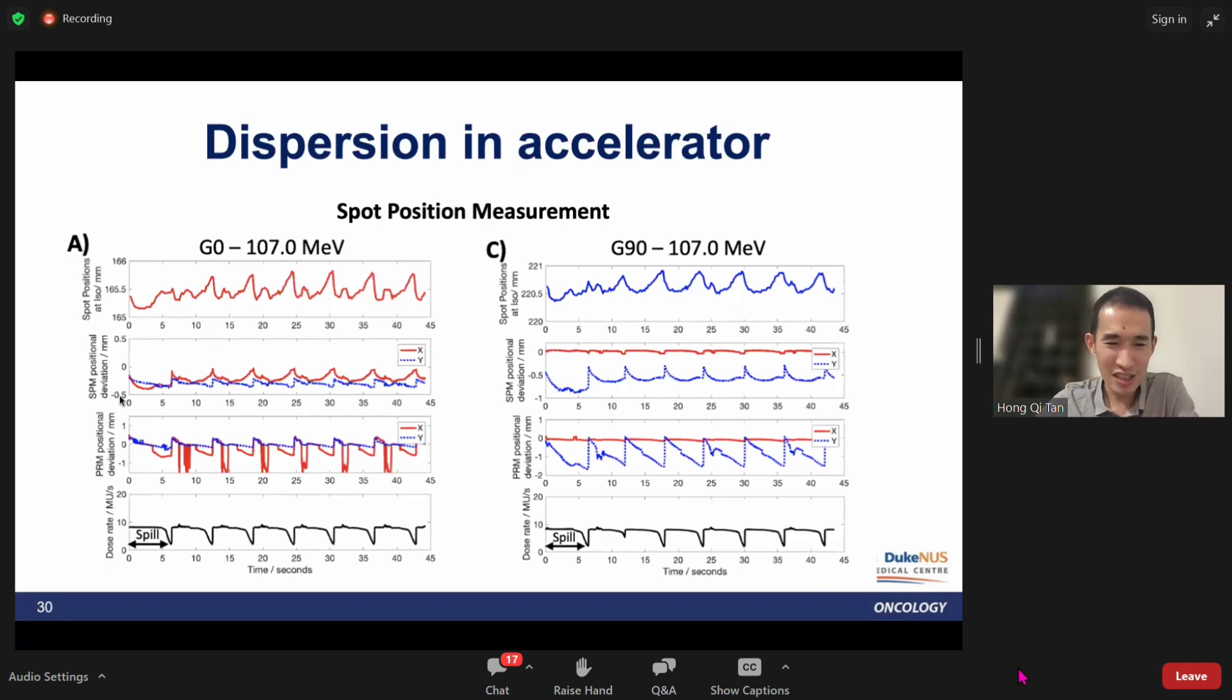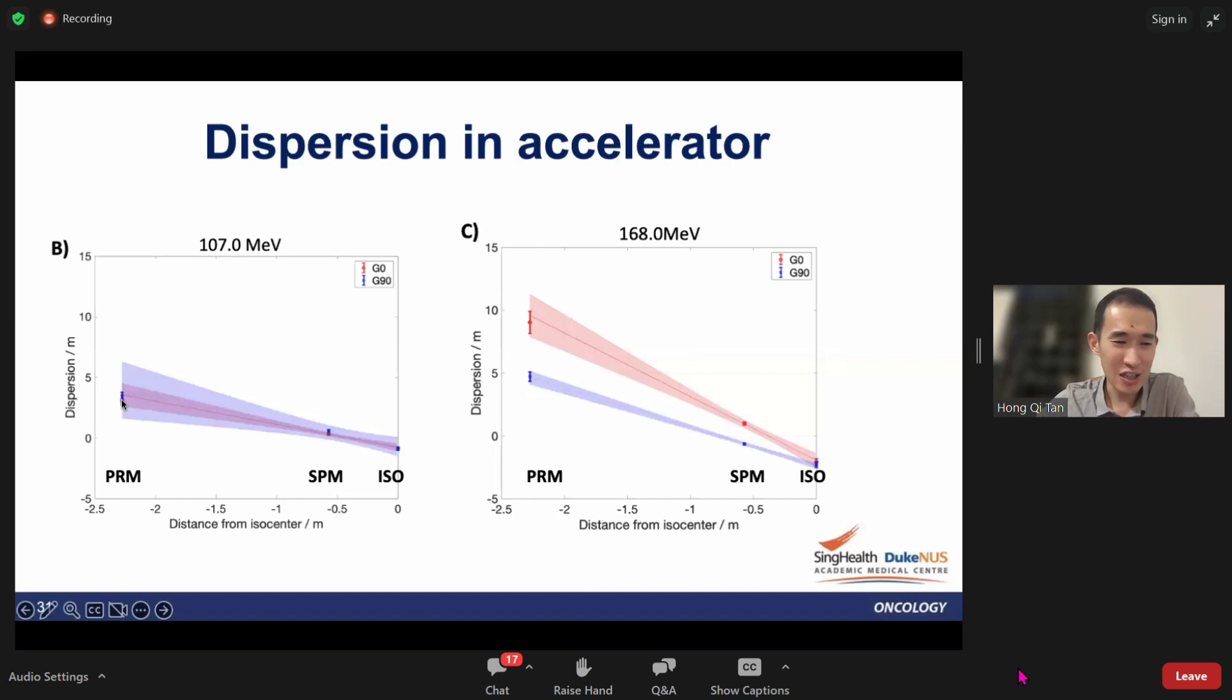With this data, we get the dispersion at the PRM, SPM, and ISO for both energies. Actually, we did this for all nine energies, but I'm showing these two just to demonstrate the idea. You can see that these three points do align along a straight line. There's no reason to expect that gantry 0 and gantry 90 should have the same dispersion profile because the bending magnet current is tuned differently based on gantry angles in the Hitachi system.